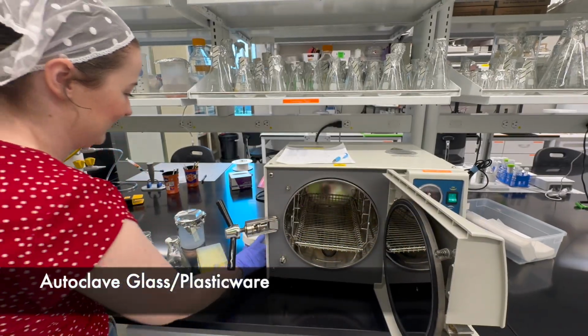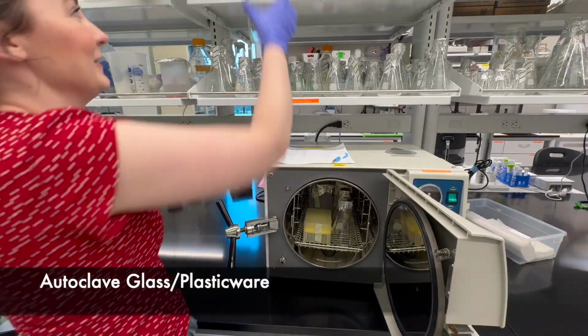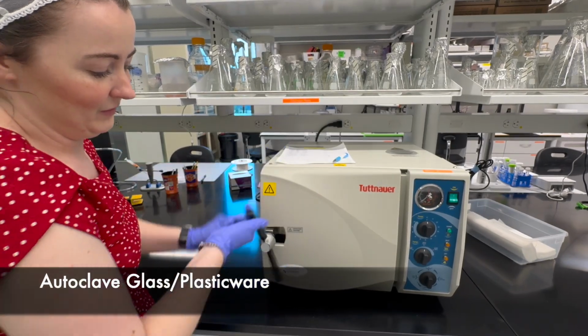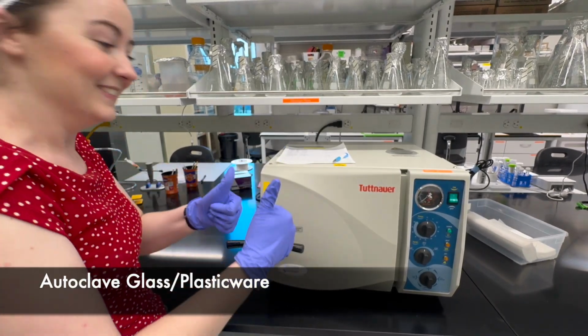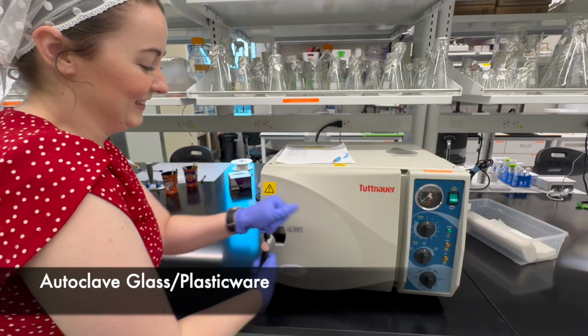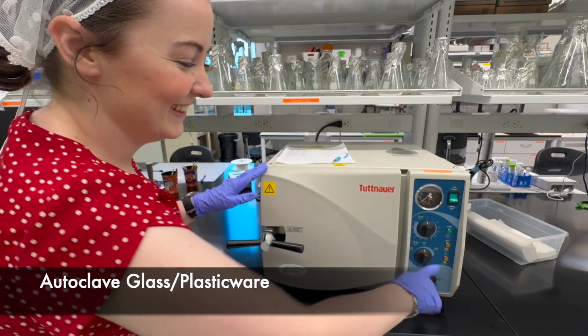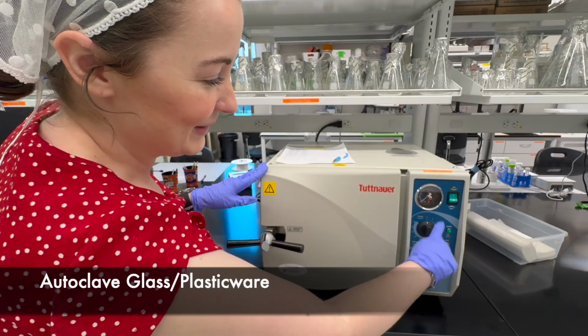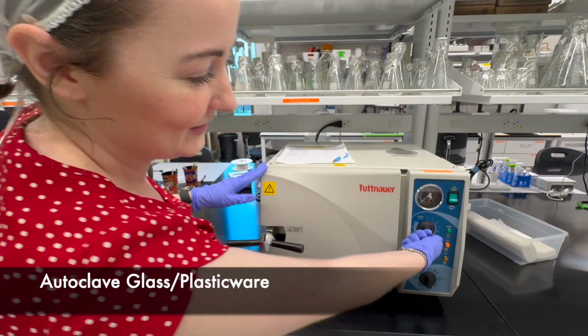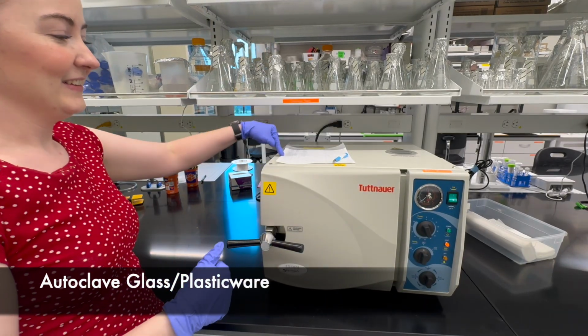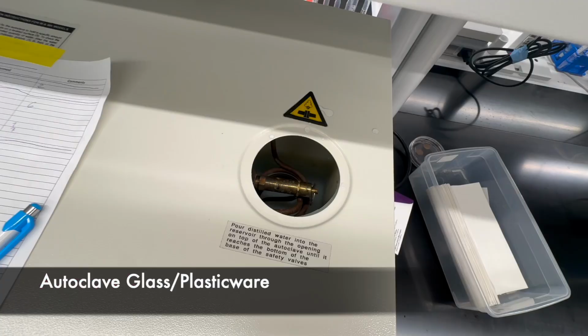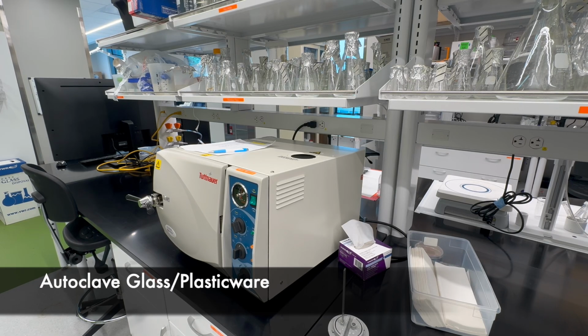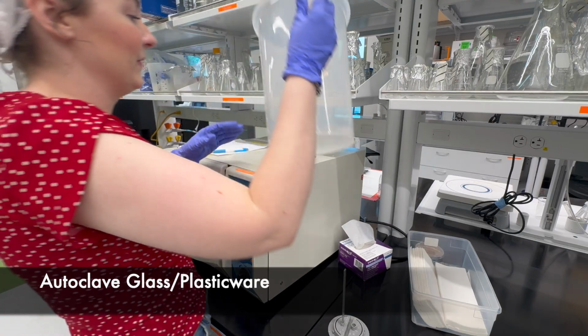Next, she is going to place all of the glass or plasticware that we need to autoclave and turn the door and make sure it's very tight. This autoclave has a couple of knobs. You are going to turn the timer to 30 for a dry cycle or 1 hour for a liquid cycle. Do not touch the middle knob. The autoclave runs on steam, so you want to make sure that this has enough water in it. The water needs to be filled all the way to the coils at the bottom, so that way the autoclave does not burn up.